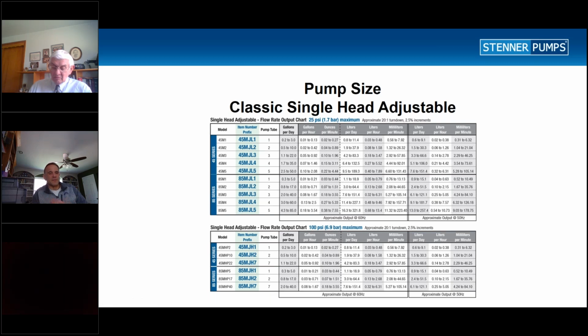So when I'm sizing a pump, the first question I would ask a customer, or I would determine, is what my flow rate needs to be in gallons per day. Based off of that, I will always try to size the pump so that, if you're using an adjustable rate pump, you're always operating it at 50% or higher, or at a level of 5 or higher on the feed rate control dial.